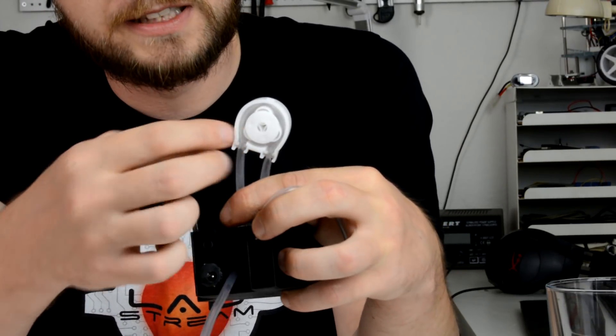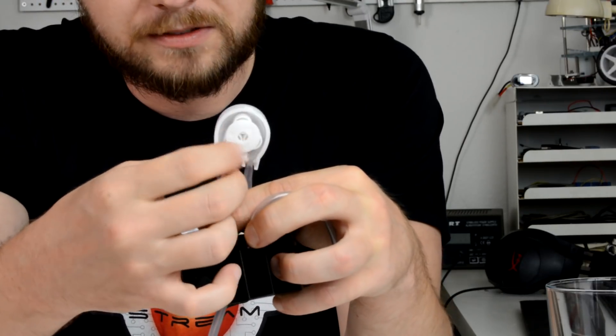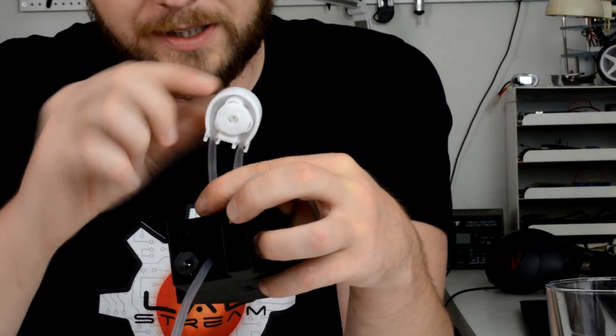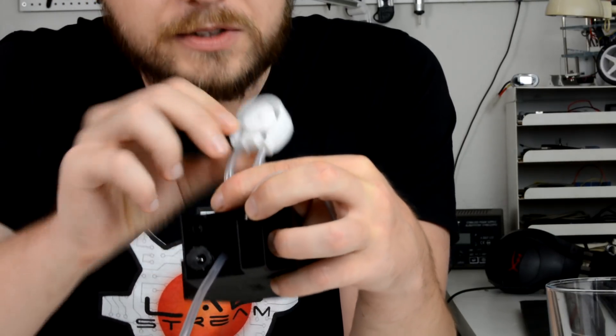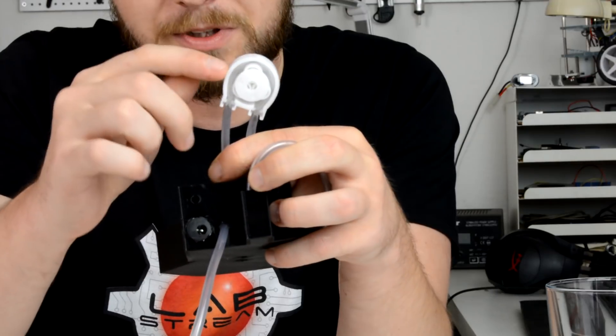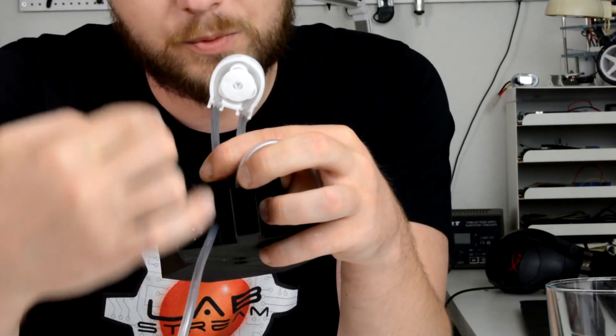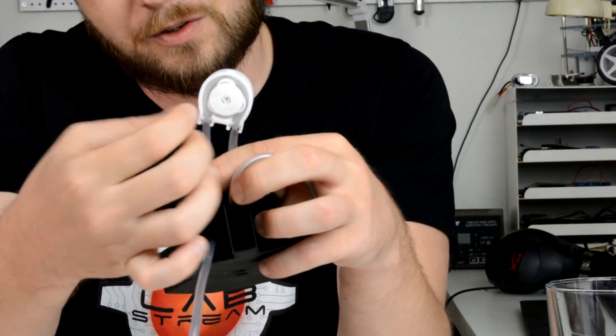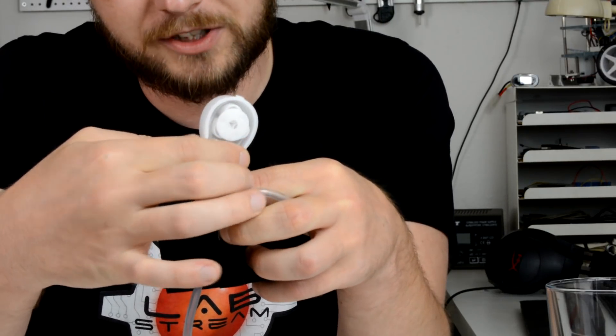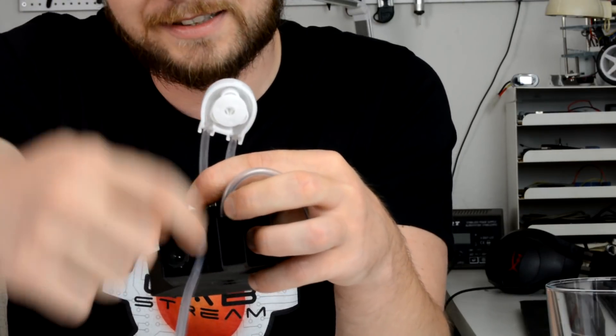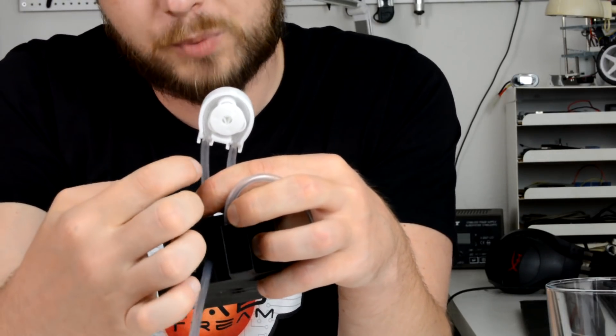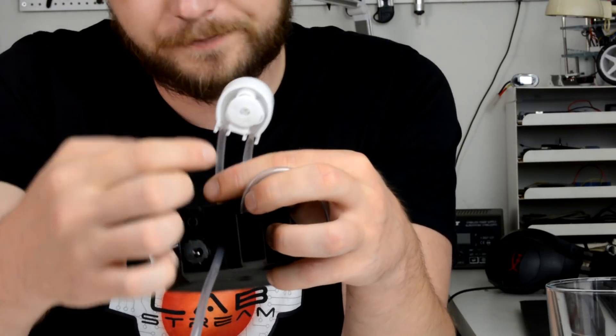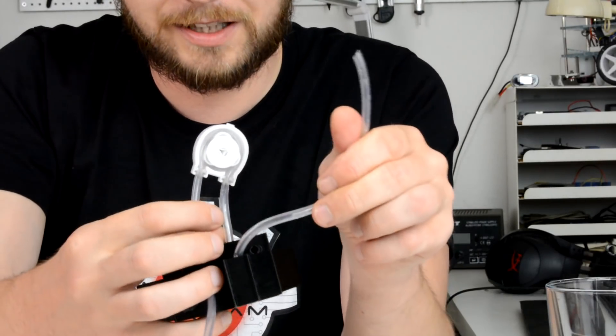Now with the bottom blade removed we can see the flexible tube which goes in on one side makes this little circle and goes out on the other side. The way peristaltic pumps work is that we have these three bearings in here or three wheels and the motor will spin them and they press on this flexible tube. When they spin they will press the liquid through this in a circular motion and they will press on here move around keeping the pressure and release the liquid on the other side so the liquid will get pressed through this hose through this flexible tube and exit on the other side.